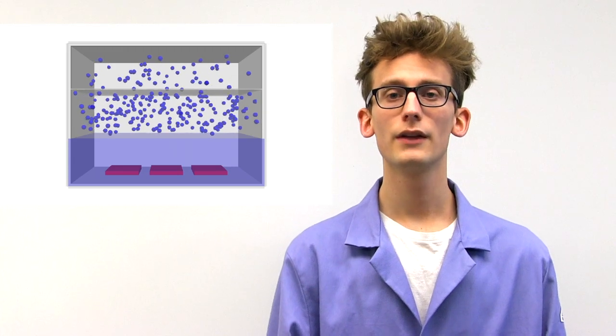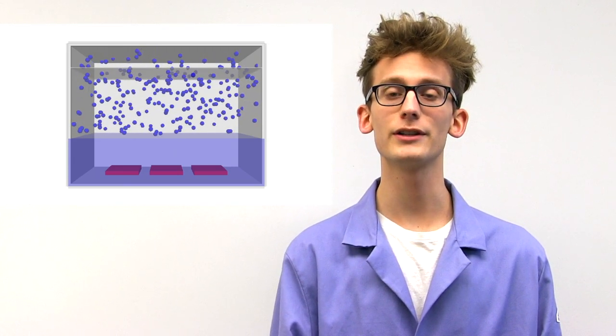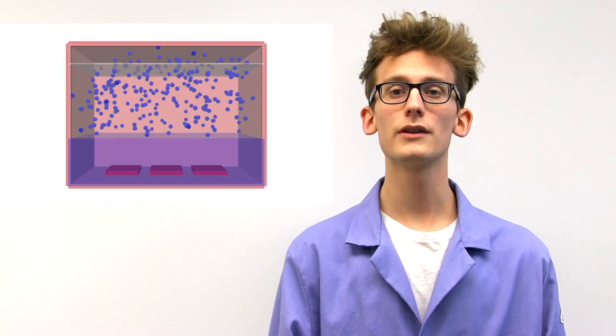The obvious solution might be to put a lid on the container. However, as the vapor layer rises, air in the headspace will be compressed, and pressure inside the system will grow rapidly. This increase in pressure can cause leaks and/or serious damage to your container. For safety, this air must be released during operation, especially on startup. This ventilation results in a small amount of fluid loss.